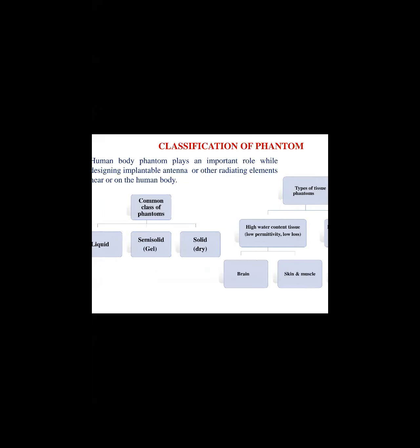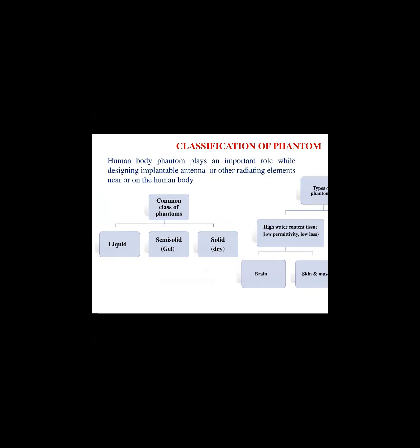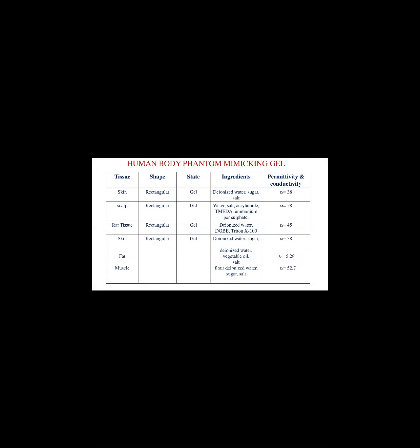If you go for any class of phantoms, in common we use three forms: liquid, gel, or solid. Most often we use a gel, combining different dielectric ingredients, and we can prepare different mimicking gels. In general, phantom models support designing implantable antennas for biological characteristics. These three are the major classification: liquid, semi-solid, or solid, based on the water content.